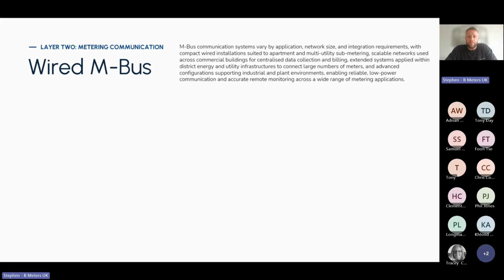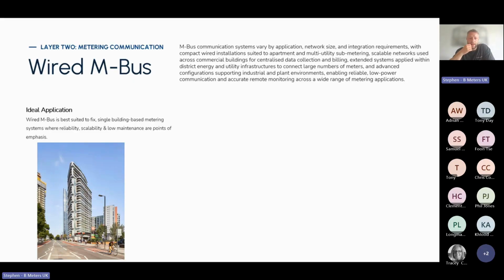Moving on to wired M-bus, which again I imagine most of you, if you get involved in metering, is probably your go-to across water, heat, and even if you're taking pulse outputs and converting them, M-bus is an easy communication to work with. An ideal application would be a single building-based metering system where reliability, scalability, and low maintenance are points of emphasis. So, for example, against a pulse output, you tend to get very restricted cable runs, whereas with M-bus you essentially run a bus, daisy chain onto it, and then you can pick up multiple meters on the same network. So it's not fixed to any one manufacturer or to any one device. Most metering manufacturers will have an M-bus solution. Most of them will work with third-party devices. So it's a very open protocol.